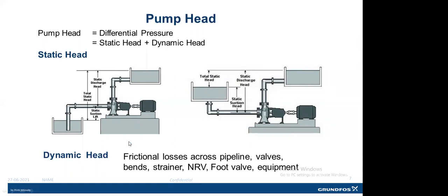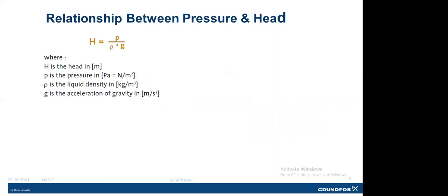And how do we measure that? Once we install the pump at site, how can we check at which head the pump is operating? We measure the differential pressure across the pump, and from pressure, how do we calculate the head? There is a standard formula to calculate the head. It's nothing but head is equal to pressure in Pascal in the numerator, and in the denominator we need to take into account liquid density and acceleration due to gravity in meter per second squared.